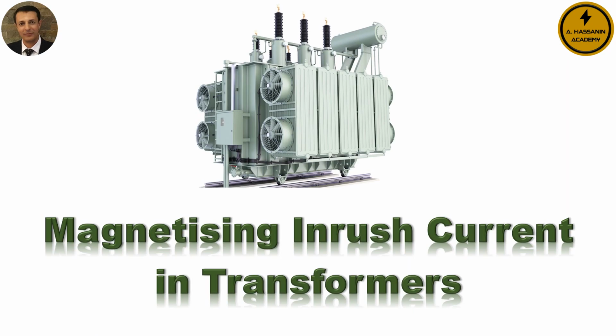That is why we are going to talk about the magnetizing inrush current, or the inrush current in transformers. We will learn together the main causes behind the occurrence of inrush current, whether it is a single type or if there are different types of this current, and how we can address or avoid the problems caused by this current. As we will see together, or as we all know, the inrush current typically occurs at the moment of transformer energization. However, the important question is, can magnetizing inrush current occur while the transformer is already in service and operating, or does it only happen at the moment of initial energization?